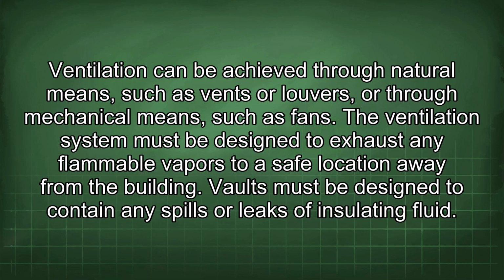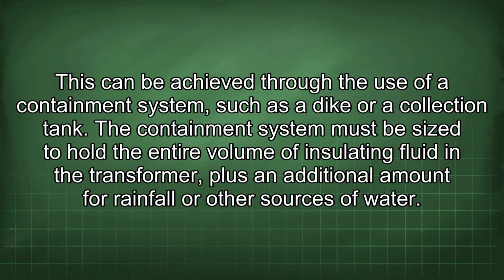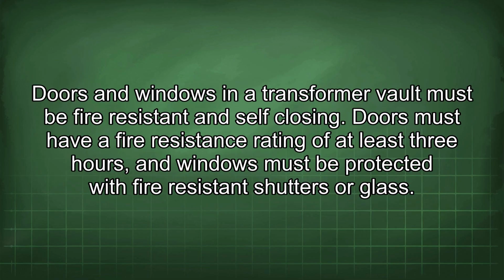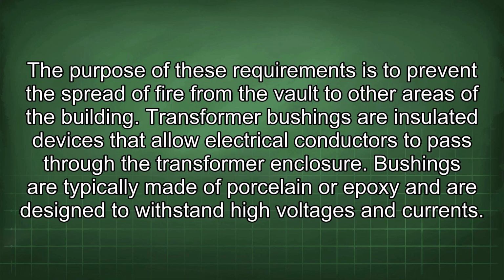Vaults must be designed to contain any spills or leaks of insulating fluid. This can be achieved through the use of a containment system, such as a dike or a collection tank. The containment system must be sized to hold the entire volume of insulating fluid in the transformer, plus an additional amount for rainfall or other sources of water. Doors and windows in a transformer vault must be fire-resistant and self-closing. Doors must have a fire-resistant rating of at least 3 hours, and windows must be protected with fire-resistant shutters or glass.